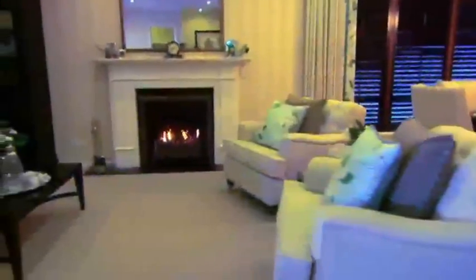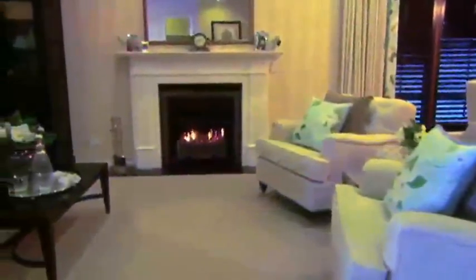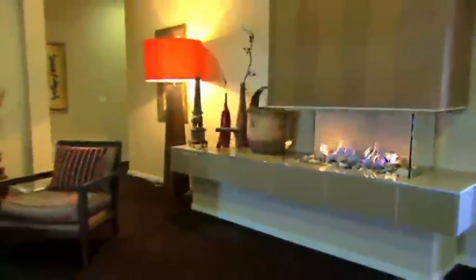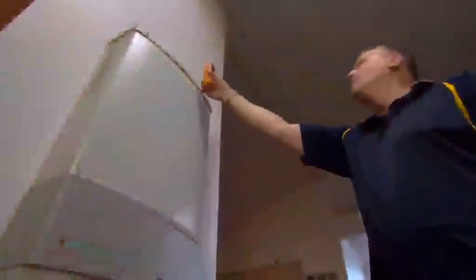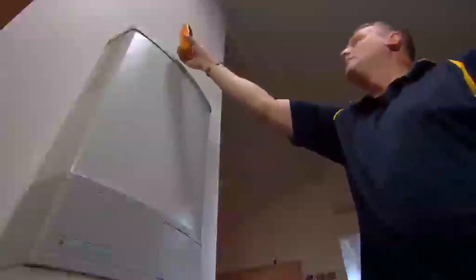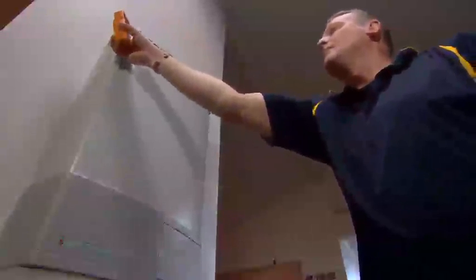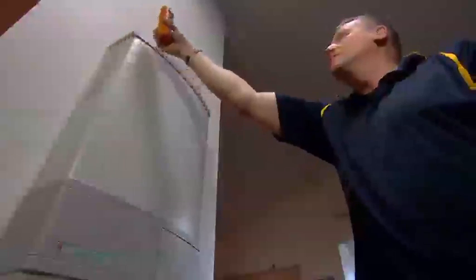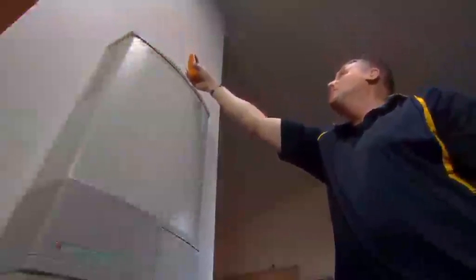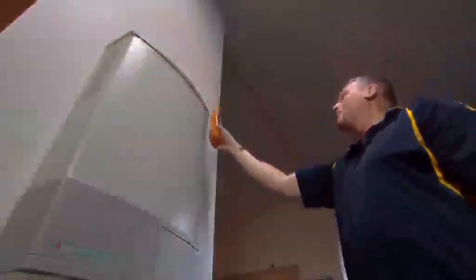In the case of decorative log effect space heaters and appliances, yellow tipping is considered normal, as these appliances are designed specifically for a luminous effect. Place the CO detection equipment sampling probe at all locations where leakage or spillage of combustion products can occur, including the draft diverter relief openings, heat exchanger joints, flue connection, and the base of flue production collection hoods.